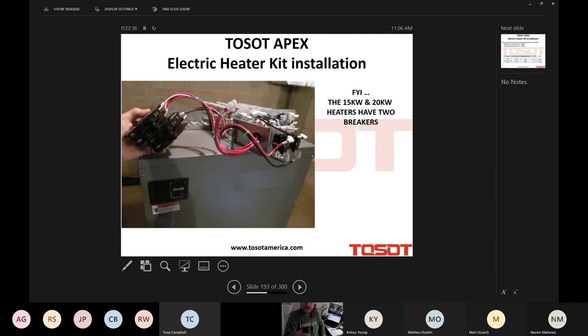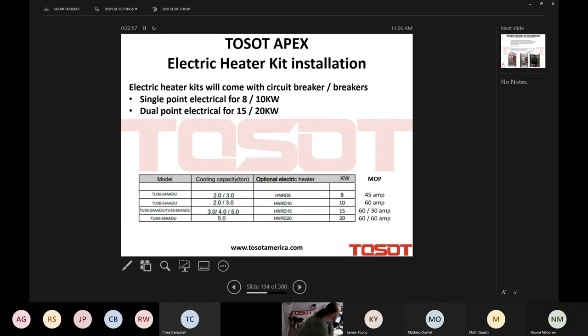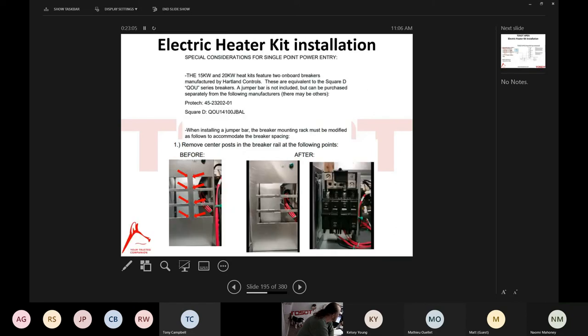This is a 20K, I believe, maybe a 15, maybe. And you can see that there are two breakers provided for the 15 and the 20. So we give you a second opportunity to mount the two breakers and also gain access to them. Maximum overcurrent protection for each of the heaters, as you can see there, from 45 to 60.